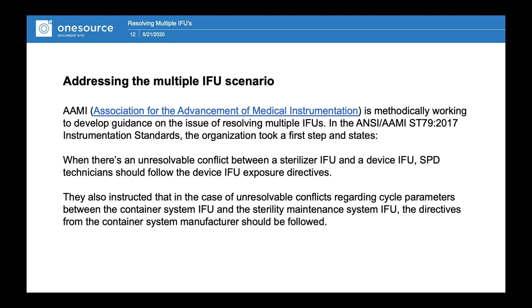And if we go to the next slide, this is directly out of the AAMI ST79 2017 document, section 10.2.2 on sterilization cycles. It says the sterilizer manufacturer's written IFU should be followed for operation of the sterilizer and indications for use. And then we have this A and B scenario, with A saying differences between the program cycle and cycle parameters recommended by the device manufacturer should be investigated and, if possible, reconciled before the items are sterilized. If there are differing instructions, the device IFU should be followed. So they're giving us guidance here to say, if it's not clear, contact the manufacturer. The manufacturer should be able to resolve that for you. They may ask you what kind of autoclave you're using. They may ask you what kind of packaging system you're using.